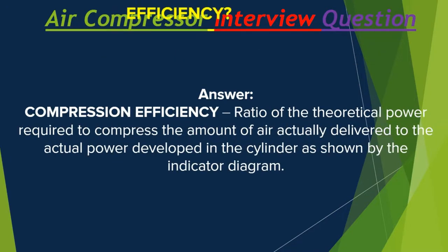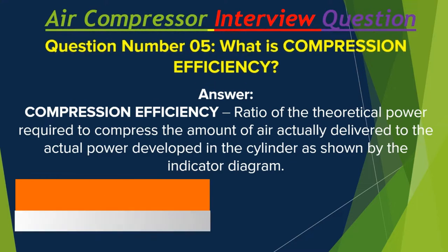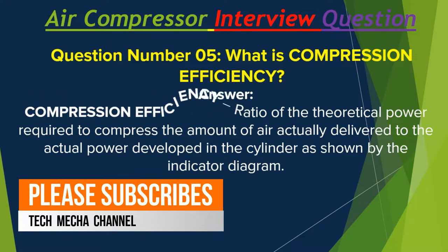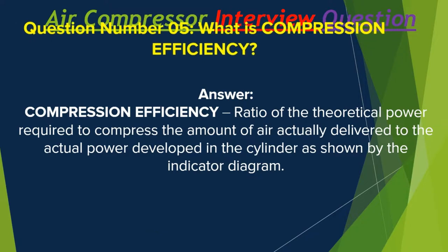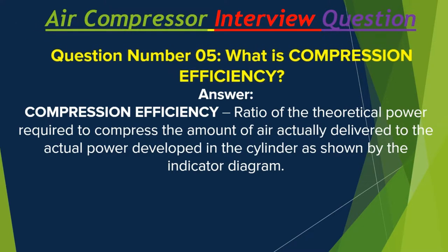Question number 5: What is compression efficiency? Compression efficiency: the ratio of the theoretical power required to compress the amount of air actually delivered, to the actual power developed in the cylinder as shown by the indicator diagram.